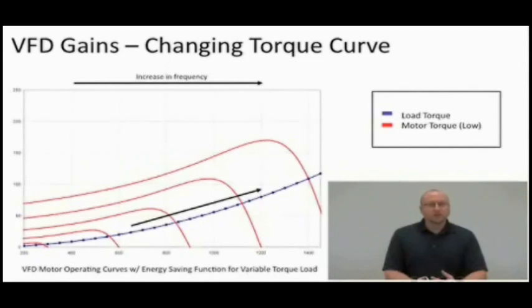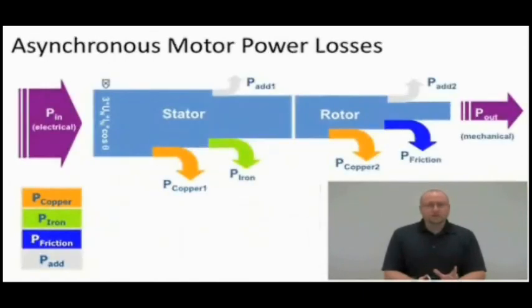For example, with this variable torque load, now for every speed set point that I'm running my motor, it's ideally loaded. I've lowered the curve to match my nominal torque rating of the motor at that speed, and that makes the system a lot more efficient. That's a lot of energy that can be saved there as well. So if we want to just look at a basic overall view, you can have a lot of gains with a variable frequency inverter.